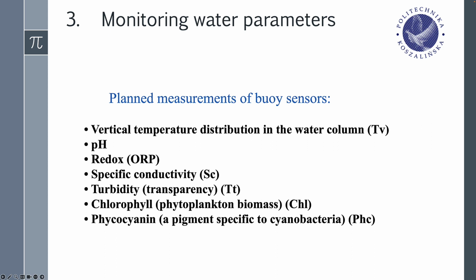4, 7, 9. Redox, ORP, oxidation reduction measurement is carried out using a dedicated probe, a combined metal electrode. It consists of a platinum indicator half cell with a potential dependent on the oxidizing reducing equilibrium in the solution and a silver chloride reference half cell with a constant potential. The parameter is calibrated based on a measurement made in a standard solution with a known mV value, 220 mV.